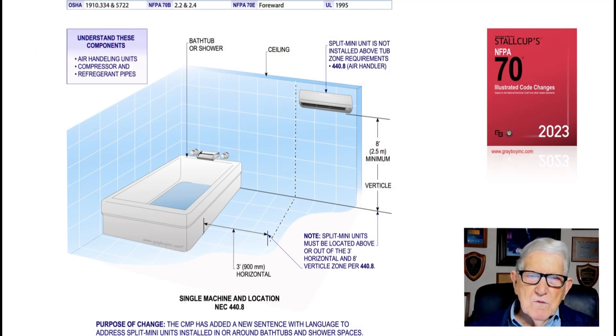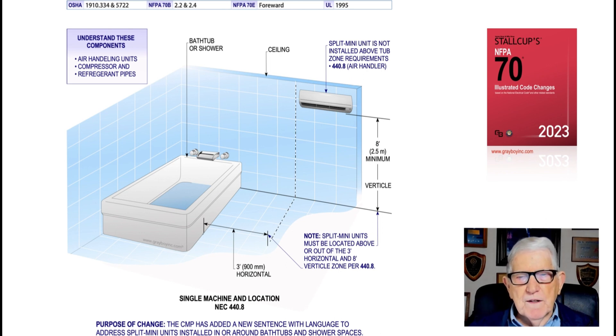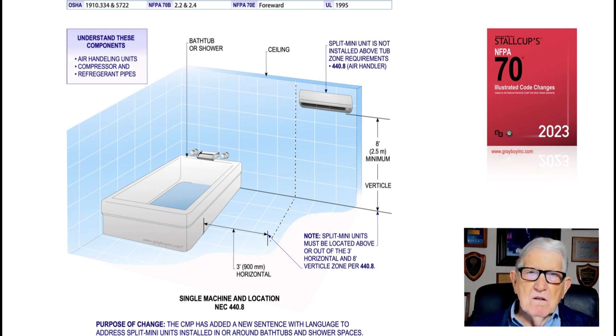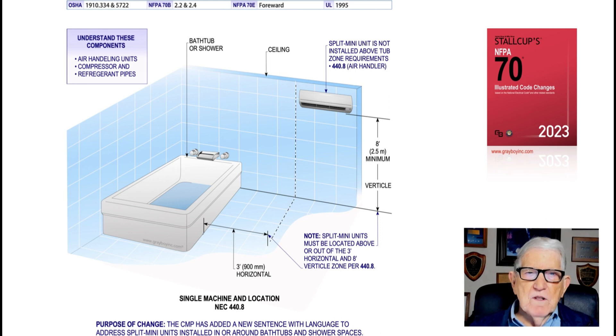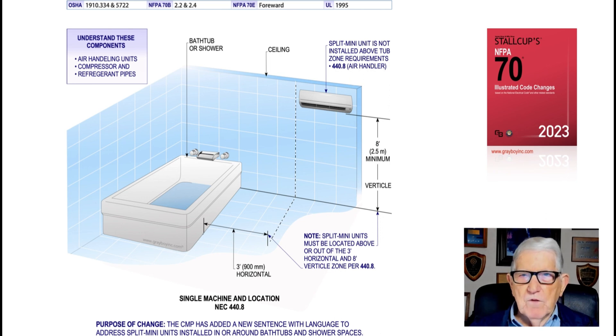This illustration deals with single machine and location in accordance with 440.8. The purpose of this change is to let the user of the NEC know that a split mini unit is not to be installed above a tub. The zone requirements of 440.8 show the unit installed out of the zone — three feet horizontally and eight feet vertically.